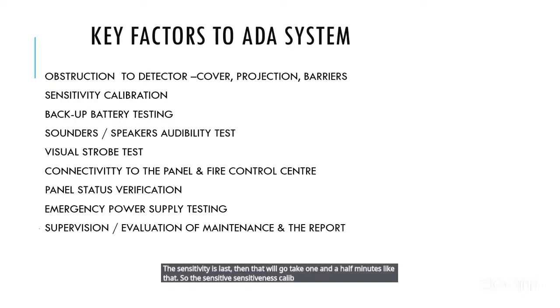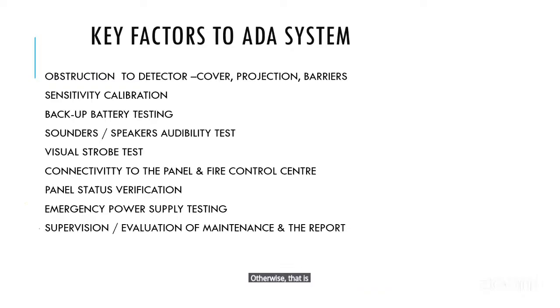calibration should be done. Normally, as per the code, you should do the calibration once in 5 years. Then a calibration certificate should be there for all the detectors. Otherwise, it is an older detector, and the detection time may differ from time to time and fire to fire.